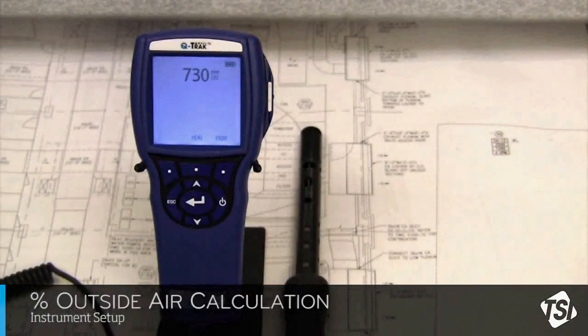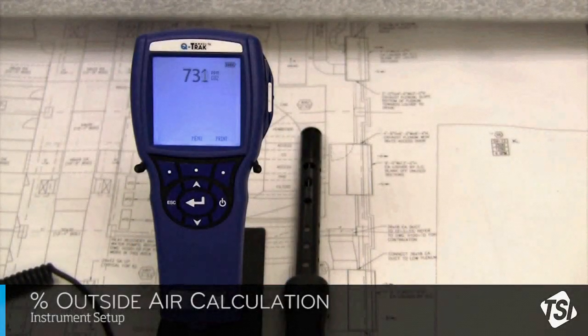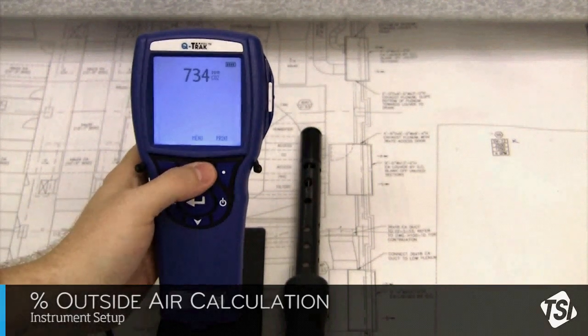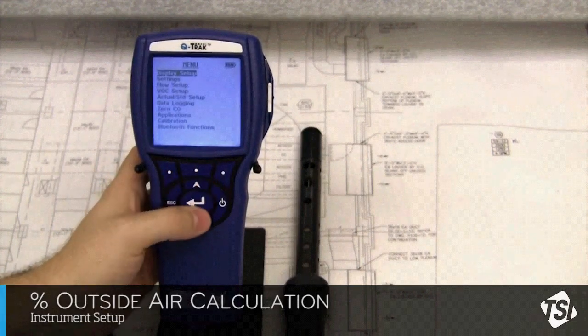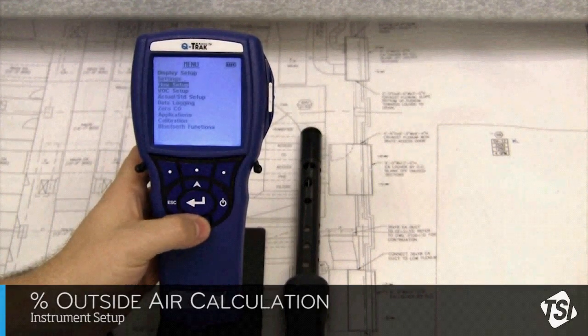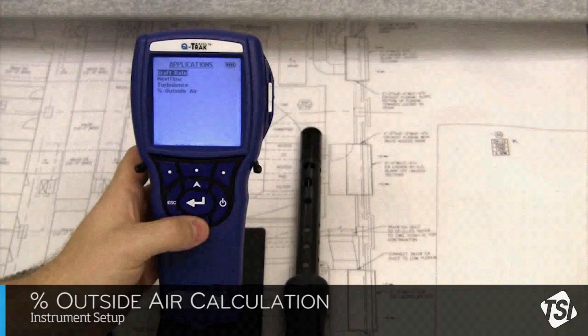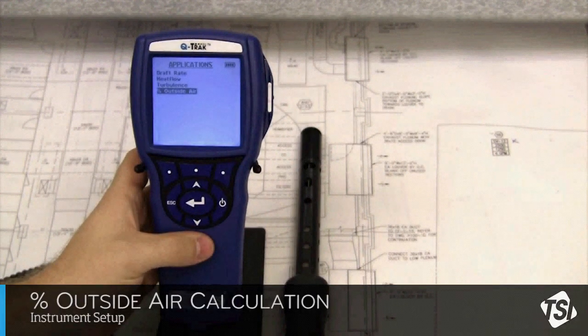Many of the TSI branded IAQ instruments make tracking these 3 necessary measurements very easy. To begin, click on Menu using the middle soft key. Arrow down to highlight Applications and press Enter to open this menu. I will then arrow down and highlight Percent Outside Air. That's our application, and press Enter to open this application.